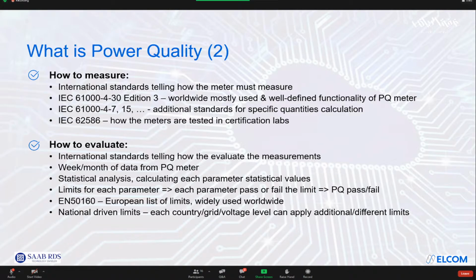So many international standards were developed. The most comprehensive one, I can say, is 61000-4-30 edition 3, which defines how power quality should be measured, what it should measure, and what the precisions should be. Also, there are additional standards like 4.7 and 4.15, which define how, for example, harmonics or flicker can be evaluated. And also there is one more international standard, 62586, which also defines how power quality meters should be tested in certification labs.